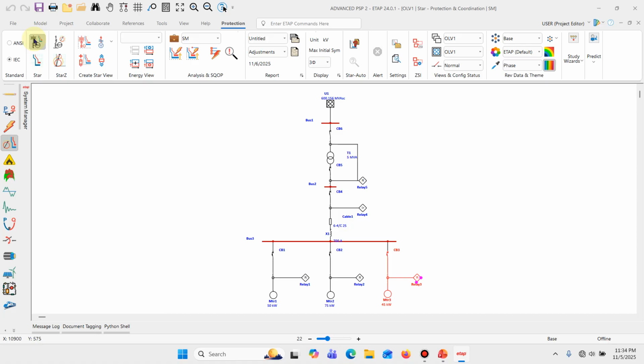So ETAP software helps us by showing the sequence of operation. It shows us overlaps or miscoordination. It shows us recommended adjustments if we are having miscoordination or improper coordination. You can easily drag curves, you can adjust settings, and you can instantly see if your coordination improves. No guesswork. No trial and error in the field. So ETAP software helps us to simulate everything before we even energize the system.